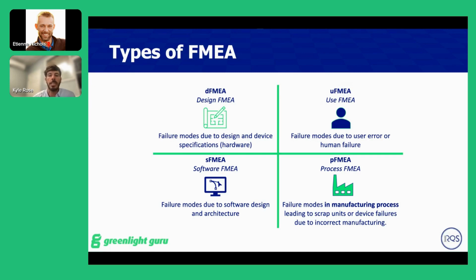A process FMEA is the step of evaluating the actual manufacturing process to see what could cause failures. So looking at the perspective of the operator actually assembling or creating your device, what could happen if they don't do this step properly, if they don't heat this part correctly, if they don't seal them together or do whatever they're supposed to do. If that fails, what would happen and how likely would we know? So these are things where the FMEA model can be used and incorporated.